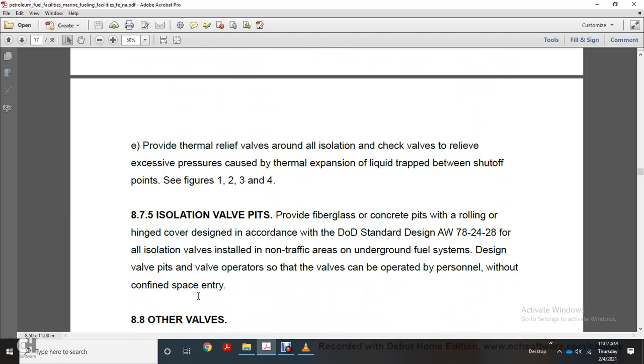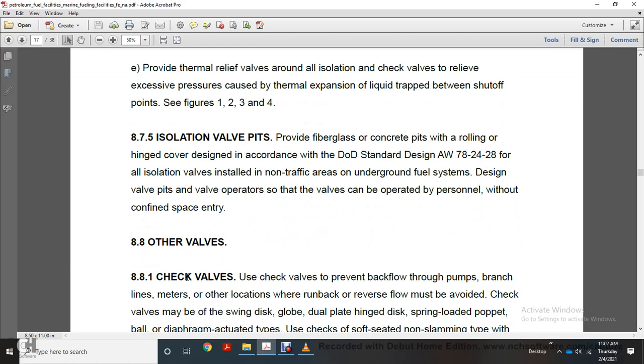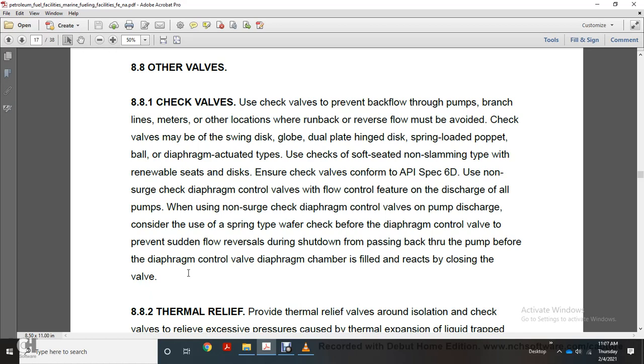Isolation valve pits: provide fiberglass or concrete pits with a rolling hinge cover, designed according to the DoD standard AW782428, for isolation valves installed in a non-traffic area of the underground fueling system. Design the valve pits and valve operators so the valves can be operated by a person without confined space entry.